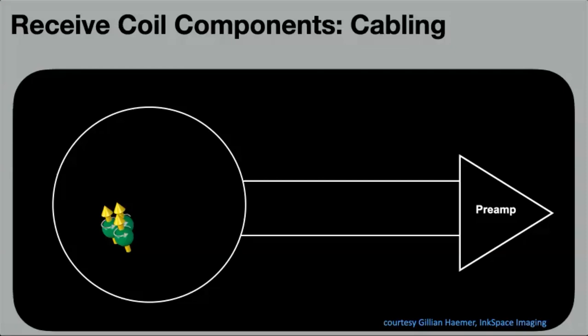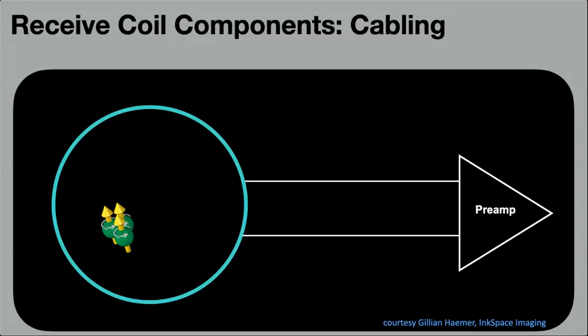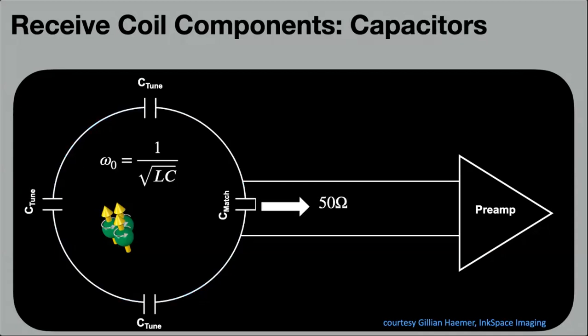Okay, so here's actually the situation. To maximize the signal, capacitors are added to create resonance at the Larmor frequency and match the impedance of the coil to the transmission line. So you've got this loop that has a certain inductance. What you do is put tuning capacitors such that the resonance frequency of the coil, or its impedance, will be the lowest at the Larmor frequency. And that would generate the most EMF at the Larmor frequency in the coil.